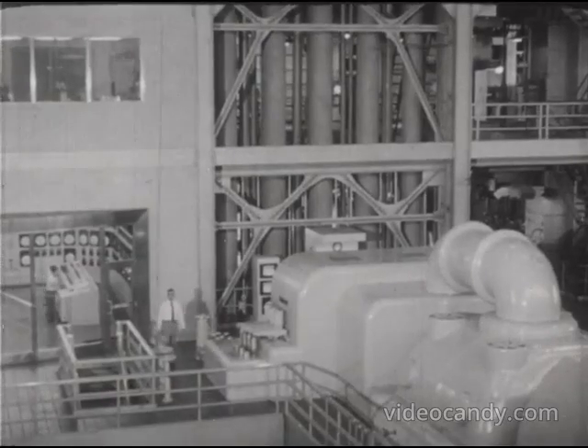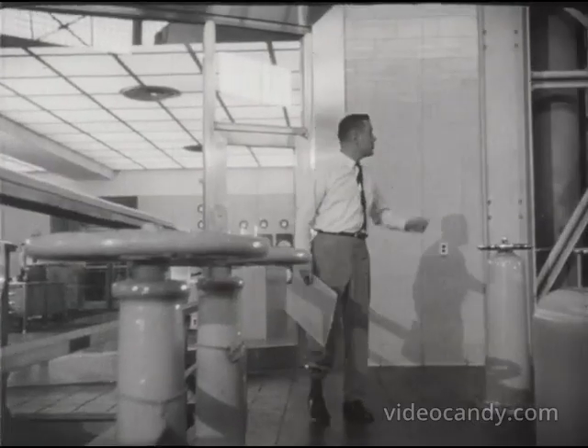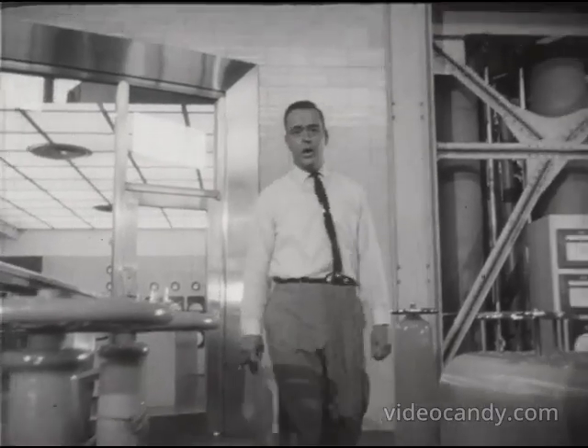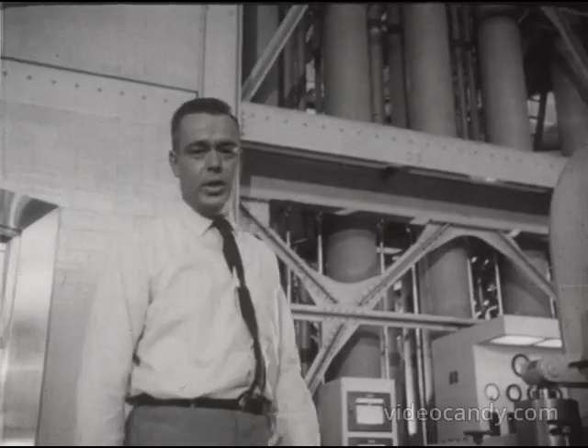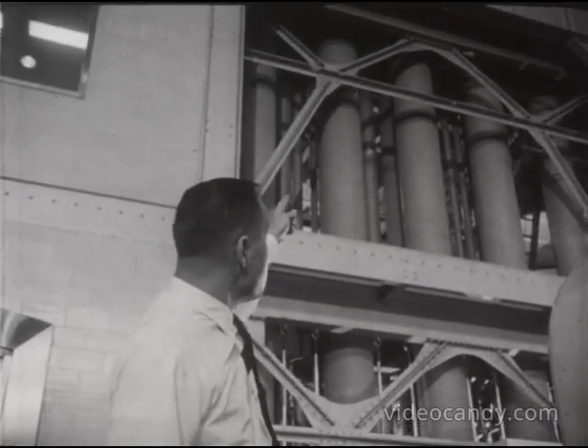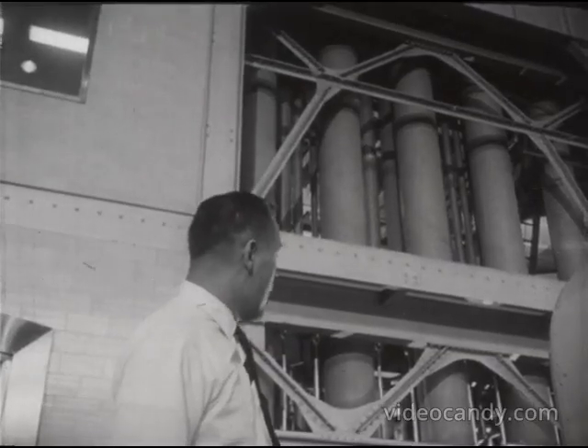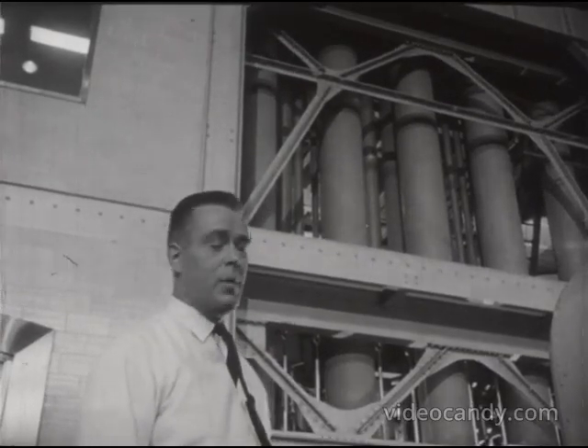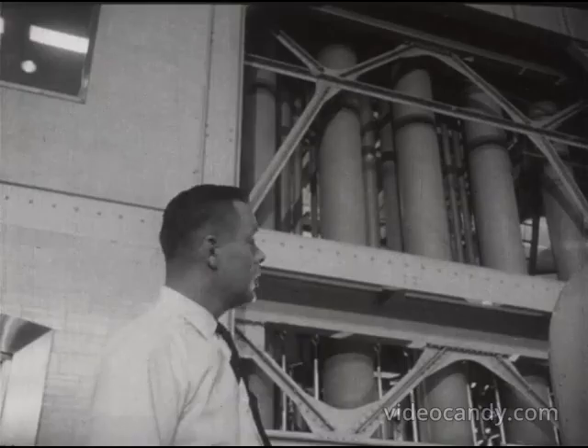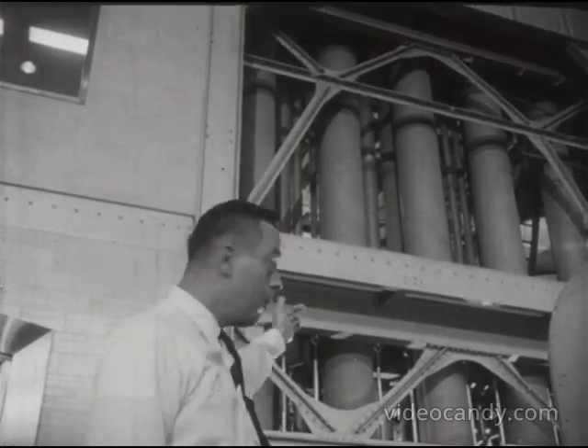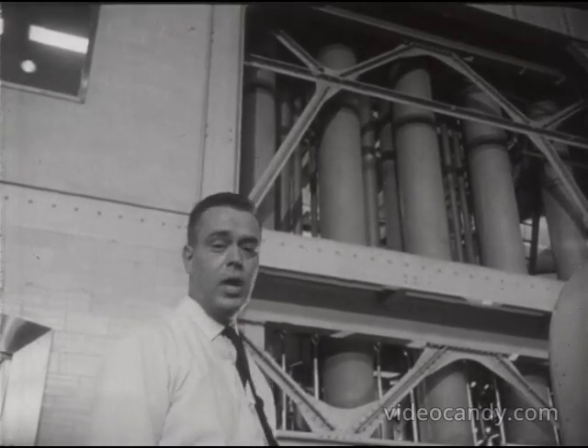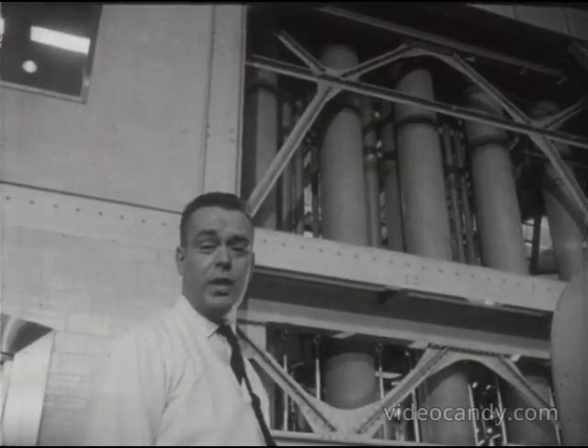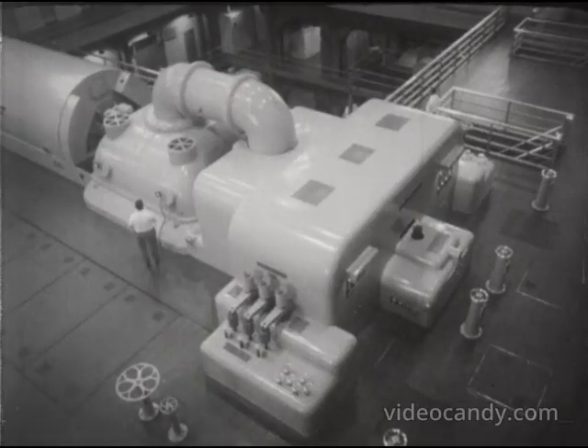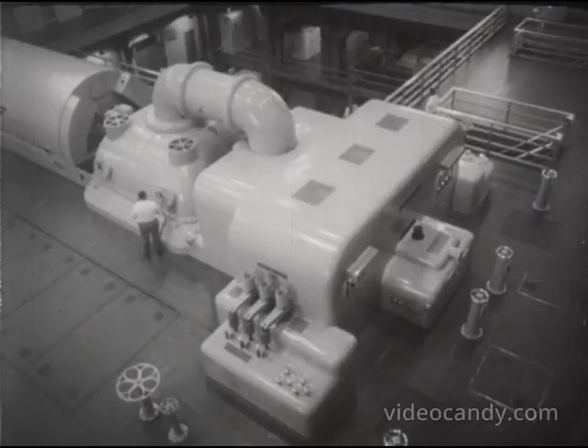Steam flows to and from the turbine through these pipes. They're well insulated in order to minimize the loss of energy into the room. The center pipe brings steam from the boiler to the high-pressure section of the turbine. Two others bring steam from the turbine back to the boiler for reheating. And the last two bring the steam from the boiler and return it to the intermediate section of the turbine.